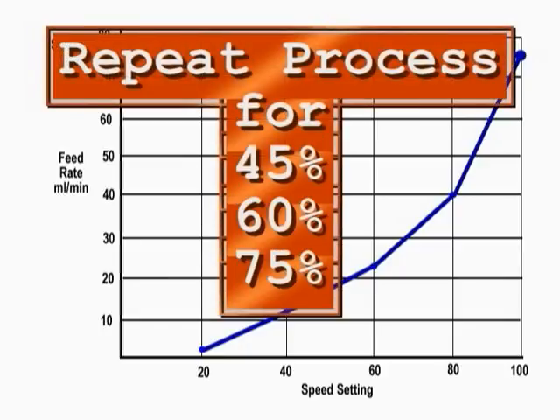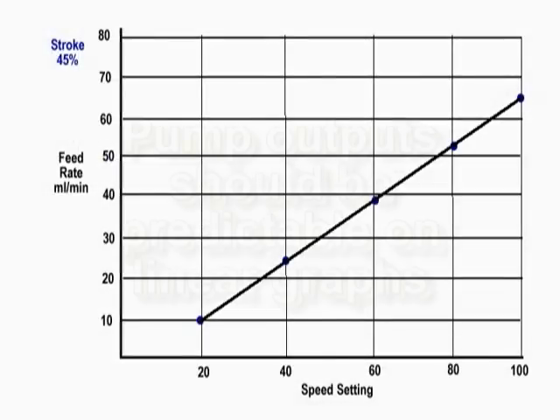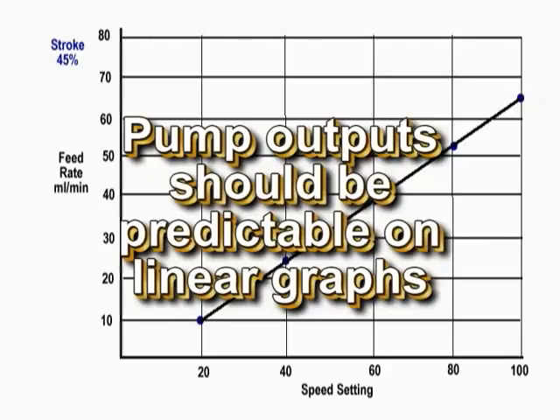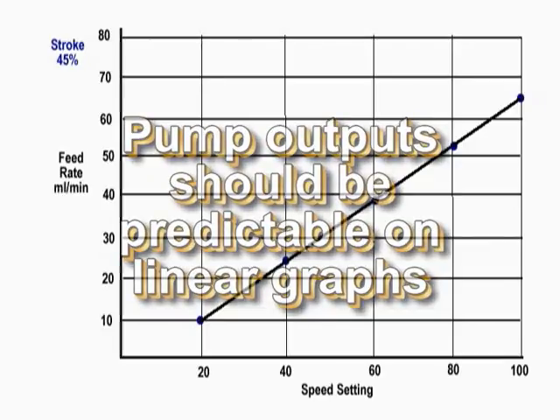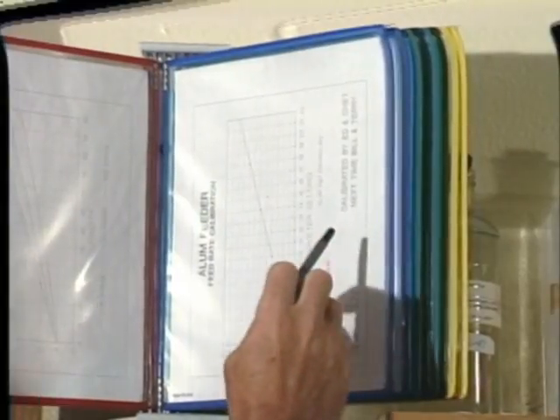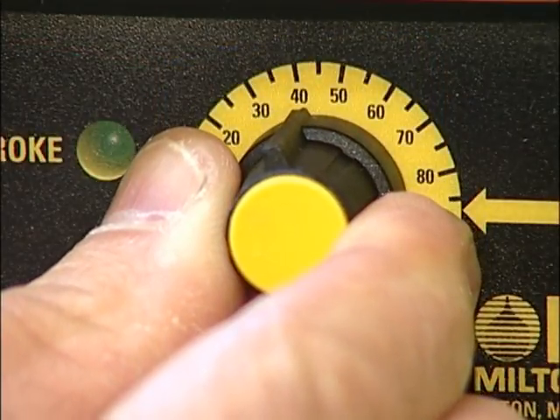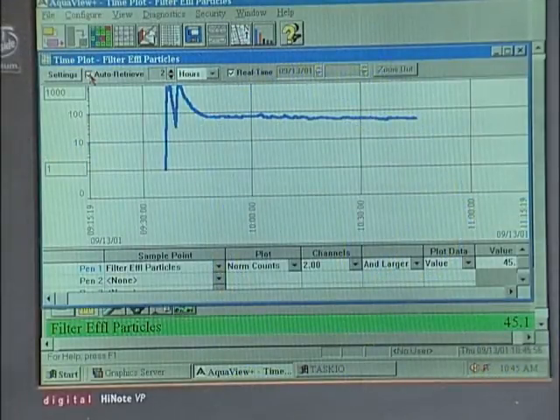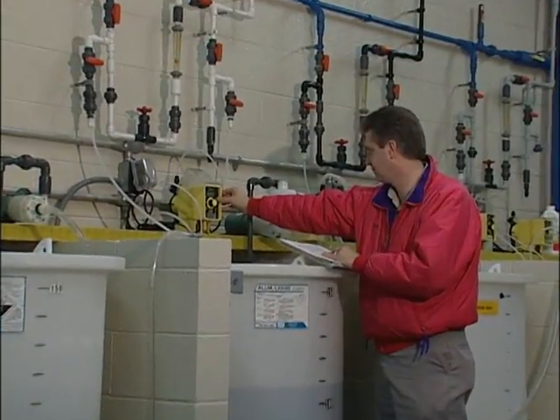The process should be repeated for stroke settings of 45, 60, 75, and 90. The operator then can compare the various results and choose the most linear curve for the normal pump operation. Operators should be able to predict reasonably well what the delivery will be at settings within the ranges established by the graph. This information should be kept near the pump in a waterproof container so it can be easily referenced when adjustments are required. Coupling this information with historical records from past events will enable the operator to make accurate adjustments of chemical feeds in response to changing water quality characteristics.